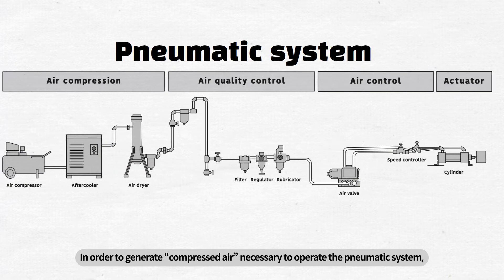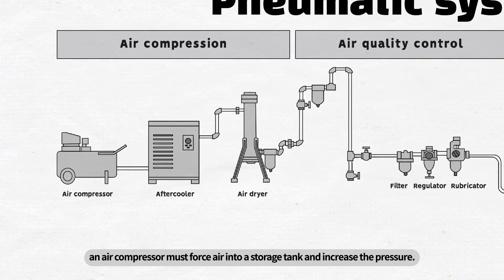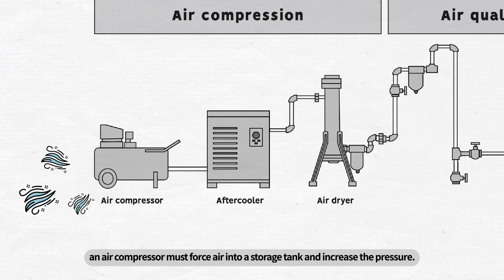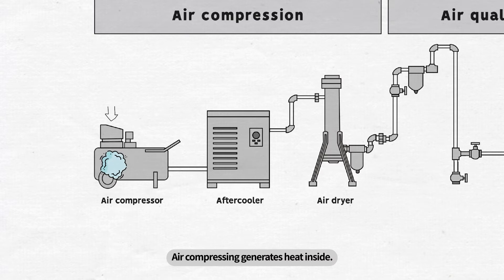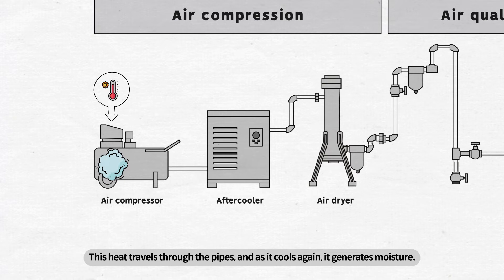When do we use it? In order to generate compressed air necessary to operate the pneumatic system, an air compressor must force air into a storage tank and increase the pressure. Air compressing generates heat inside. This heat travels through the pipes, and as it cools again, it generates moisture.